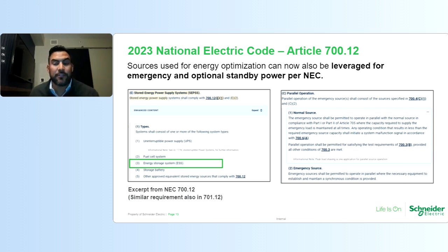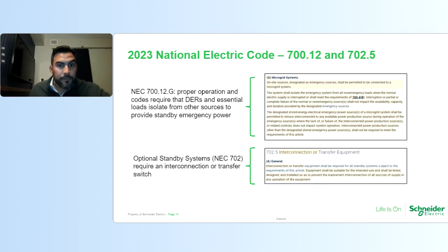You just need to ensure that if you intend to use that energy storage system in parallel operation with the utility or normal source, it has at least 2 hours of runtime. So in the event of an outage, you can disconnect from the primary source, and there's enough energy capacity to provide at least 2 hours of runtime to your emergency loads. Also, as we dive through, you'll see a section G, microgrid systems. And essentially what it highlights here is that the system shall isolate the emergency system from all non-emergency loads when the normal electric supply is interrupted.